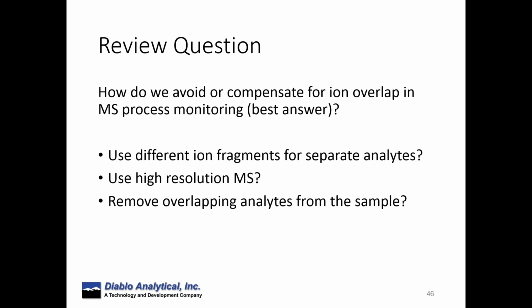The other example is removing overlapping analytes from the sample. Well, that would be great, but it's not always possible. But for example, if we're looking at a syngas and we want to measure carbon monoxide, then we might design our process so that we use argon as a purge gas in the system versus nitrogen, because carbon monoxide and nitrogen, N2 and CO, both generate a signal at 28. So that would be an example where we might actually adjust or remove something that was in our experiment to avoid an overlap.